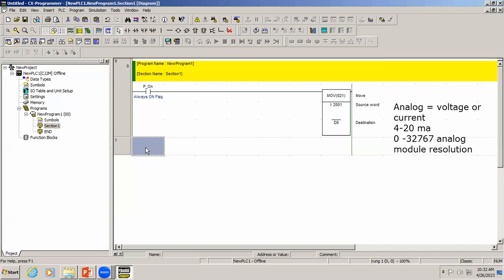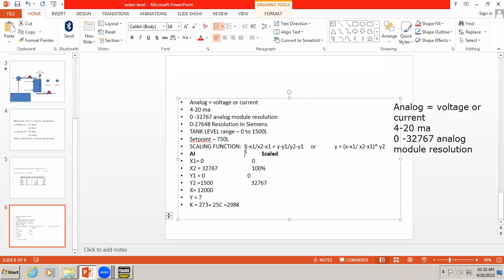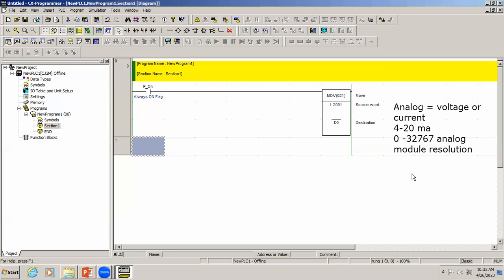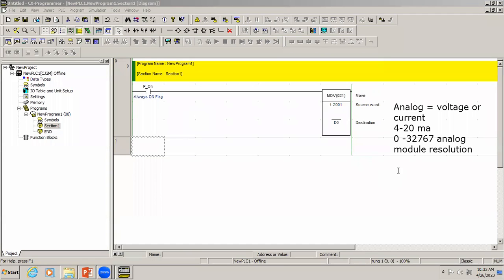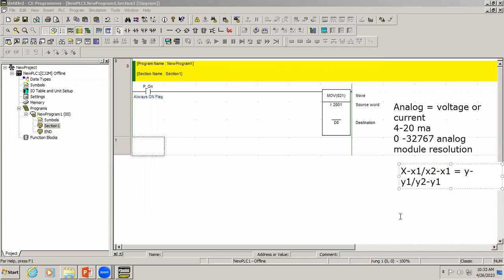For that we are going to use a scaling block. Normally the scaling block is just a mathematical calculation we learned in college. The formula is: (X − X1) / (X2 − X1) = (Y − Y1) / (Y2 − Y1). This calculation is provided as a block called SCAL — the scaling function.